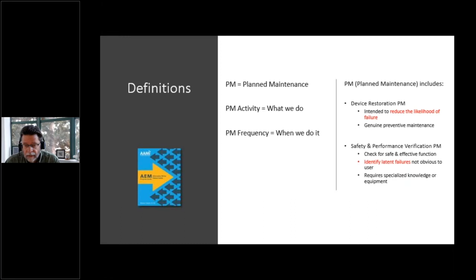So PM has two aspects, and I like to highlight this because some people make the point that PM is preventive, meaning we only do things that actually prevent future failures. And that's the first point here, device restoration. You return the equipment to its normal operating conditions, replace batteries, clean filters, whatever it takes to get it back as close as you can to new, but at least to good functioning, safe and functional condition. I would call that genuine preventive maintenance because that prevents future problems. Replacing the battery early enough reduces the likelihood that it's going to fail unexpectedly down the road.